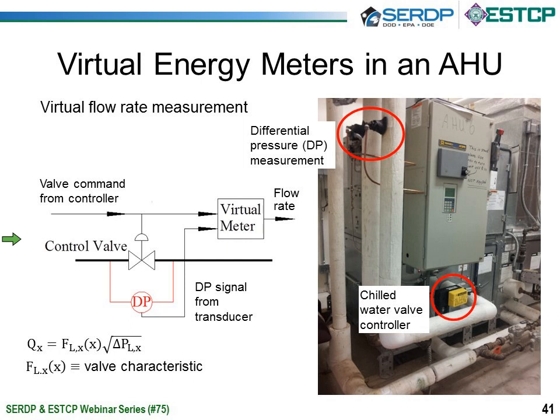In addition to that, running inside the virtual meter is a flow rate equation that we fit to the valve itself, the specific valve itself. This is indicated by the equation below the diagram. Qx, which is the flow rate, is equal to F, which is a function of X, which is the valve opening position, times the square root of the pressure difference across it, delta P. And F is the valve characteristic that changes as the value of the opening changes.